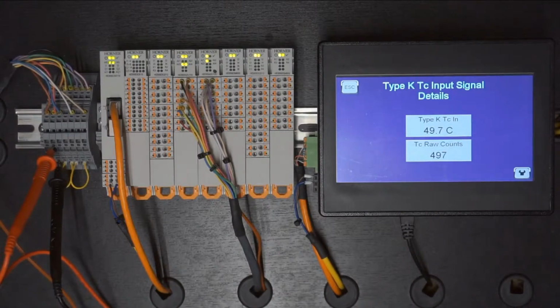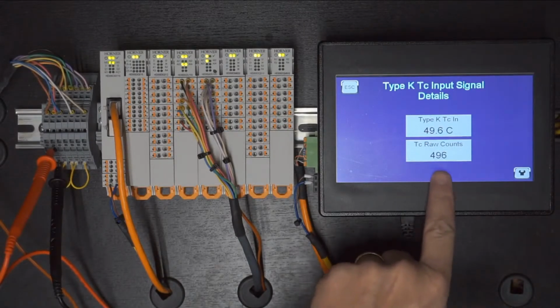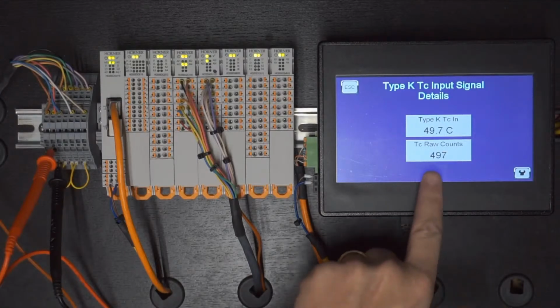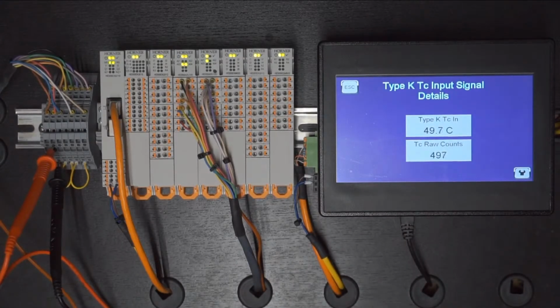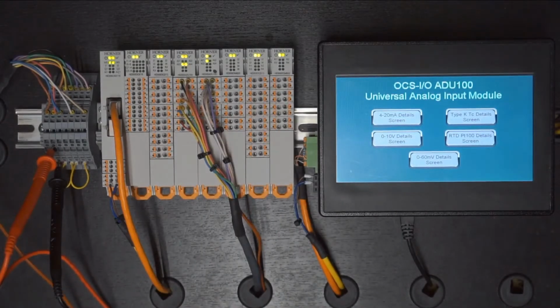Again, pretty close to 50 degrees. You can see the counts is 10 times the actual temperature because it's in 10th degree increments, and I chose degrees Celsius here. Okay, let's go ahead and go to 500 degrees. And you can see we respond based on our filter setting, and we're up to pretty close to 500 degrees. So that's thermocouples. Next, let's take a look at RTDs.